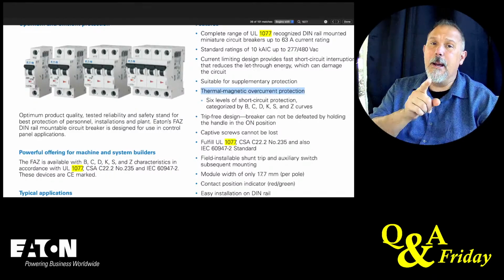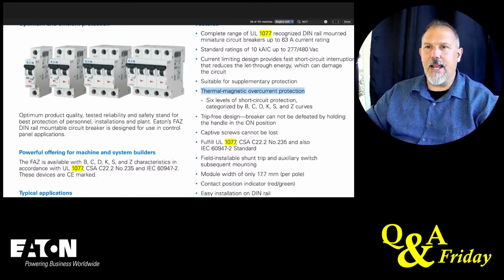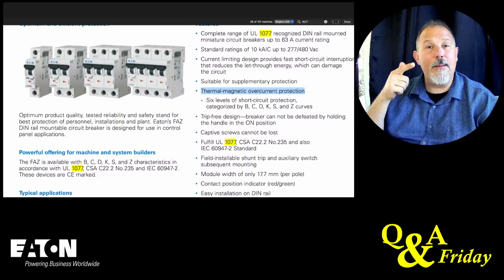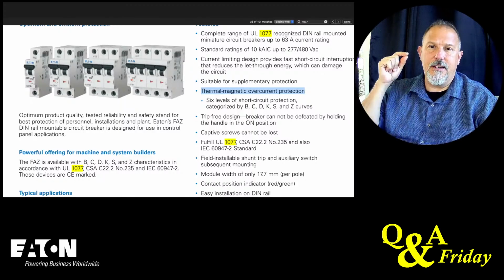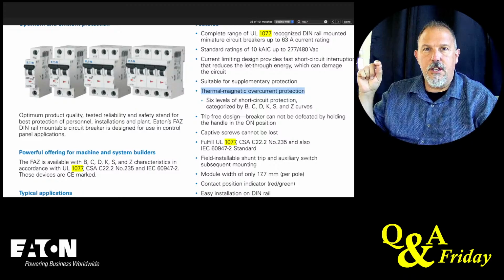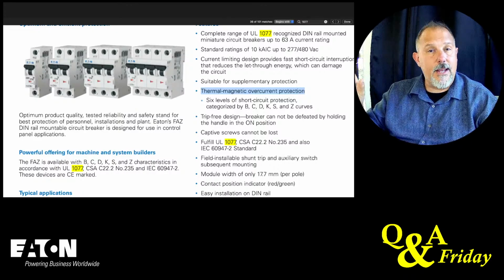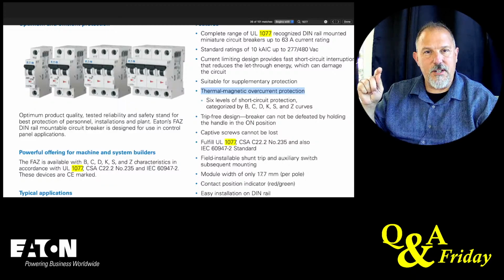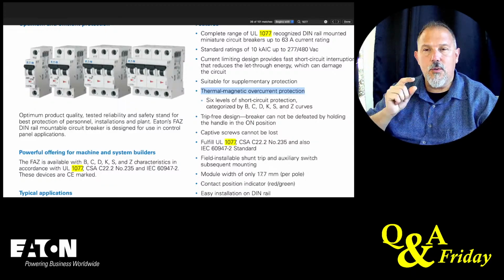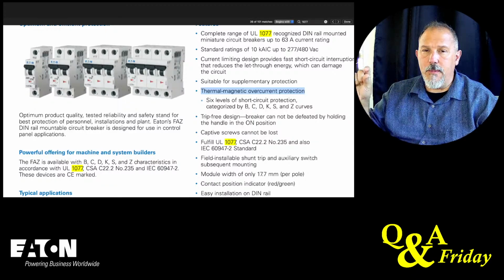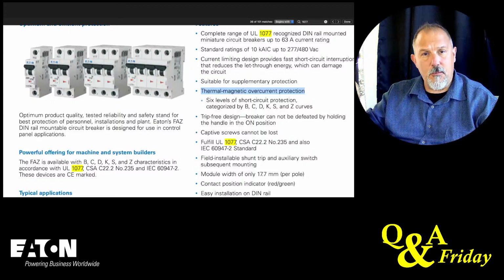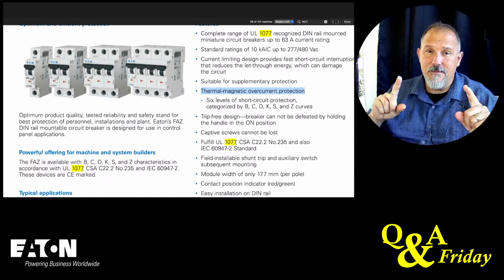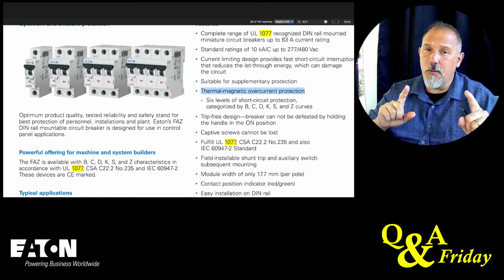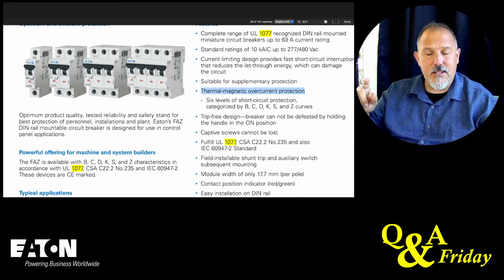And what that immediately tells you is that this device is going to have an instantaneous region. That's the magnetic. And it's going to have an overload region. That's the thermal. So it will provide thermomagnetic protection of whatever is connected to its terminals, but it's not a branch circuit overcurrent protective device because it's not listed to UL 489.